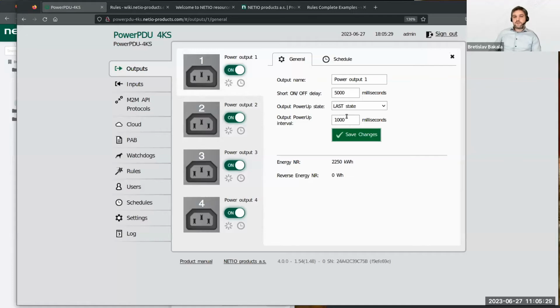What's nice about this absolute specification is that once you have, for example, 3 devices spread over a room - since you can't use just one device because you need more places to control, but everything is connected to one circuit breaker - you can set the first device's delays at 1, 2, 3, 4 seconds, the second device at 5, 6, 7, 8, and the last at 9, 10, 11, 12. This means you can set the power up sequence for all devices as if they were one device in total - that's the nice thing about this absolute setup.